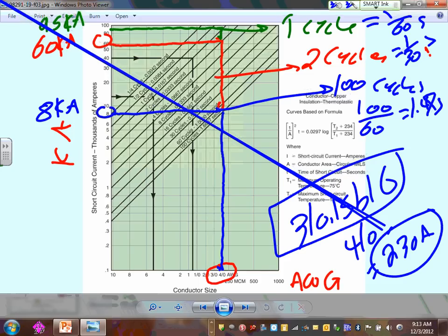I did this training for 16 hours, and I had an old-timer electrician. He said, Chad, I've been in the industry for 30 years, and I've never heard about sizing conductors based on short circuit. I said, have you ever dealt with medium voltage? He said, no. I said, that's why. You might work all your life not hearing about sizing based on short circuit. But the minute you touch anything higher than 600 volt, that's a major factor. You start to resize based on this in medium voltage. How much short circuit? How do you set your relays? The relays on the medium voltage circuit breaker will decide what size of conductor you're going to use at the end of it.